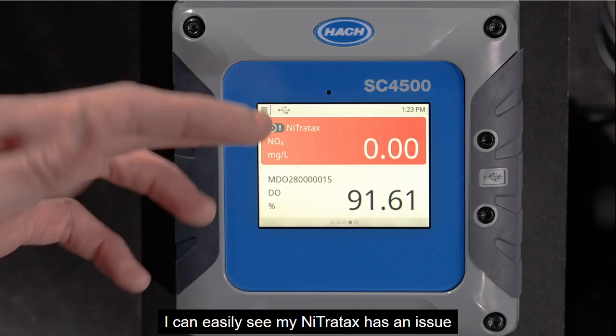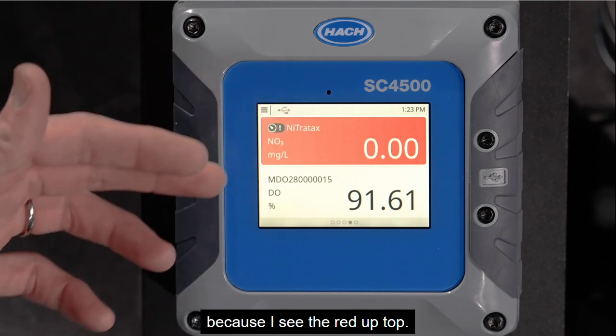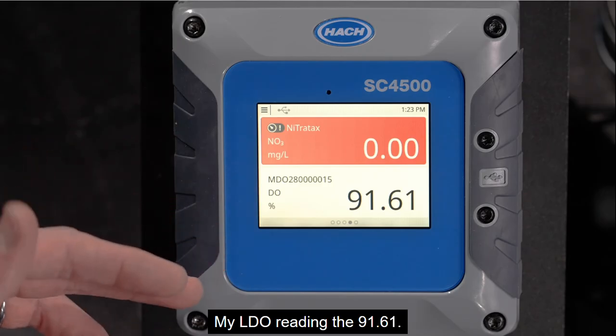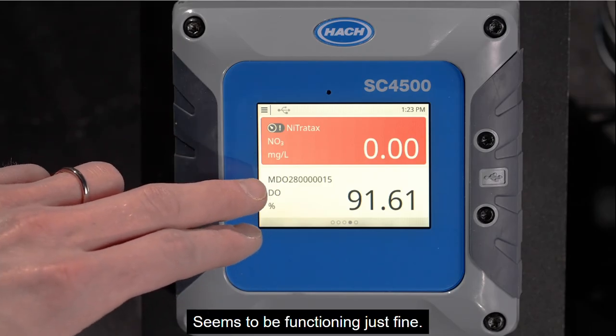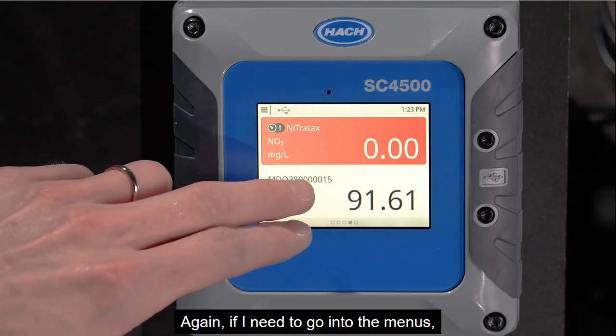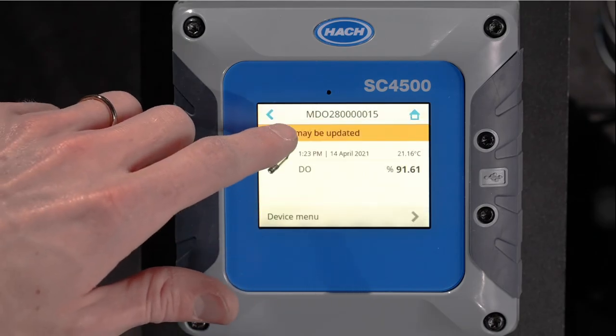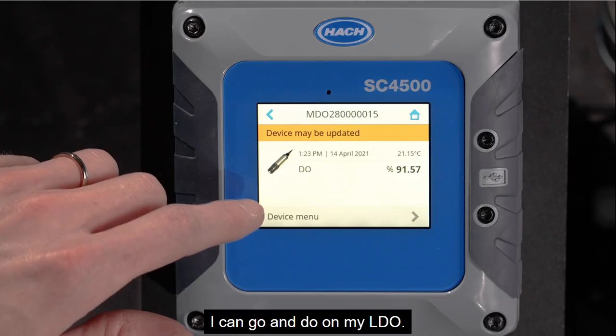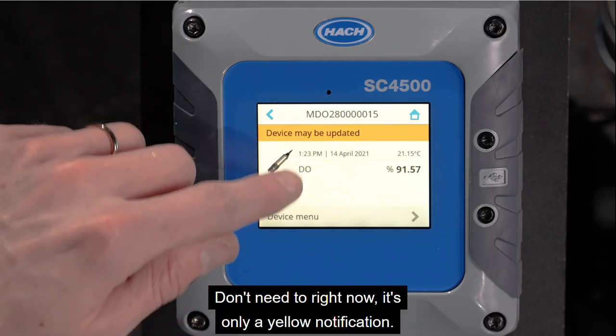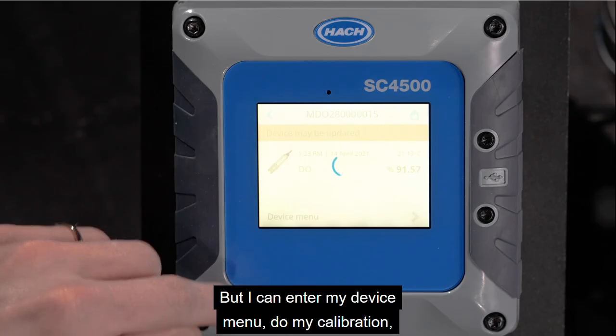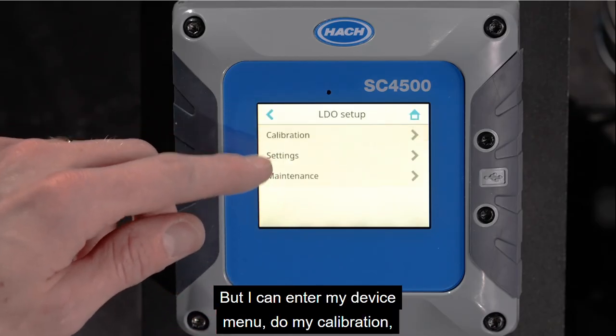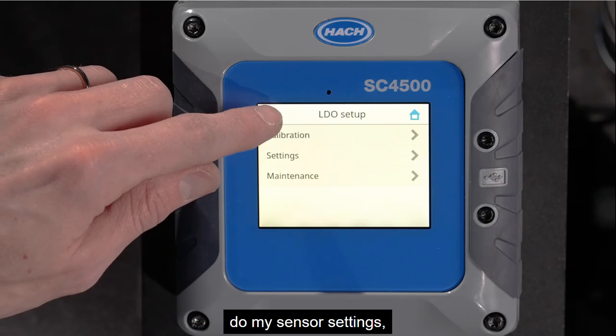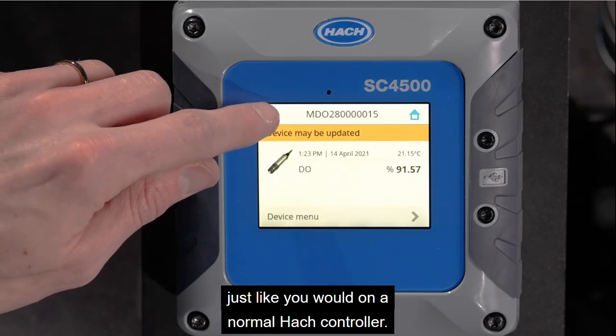I can easily see my NiTratax has an issue because I see the red up top. My LDO reading, 91.61, seems to be functioning just fine. If I go into the menus, it looks like I have a firmware update I can do on my LDO, but I don't need to right now since it's only a yellow notification. I can enter my device menu and do my calibration and sensor settings, just like on a normal Hach controller.